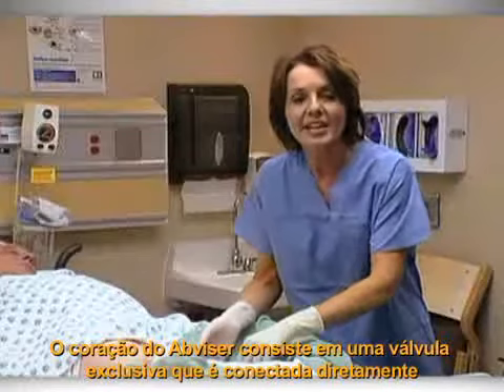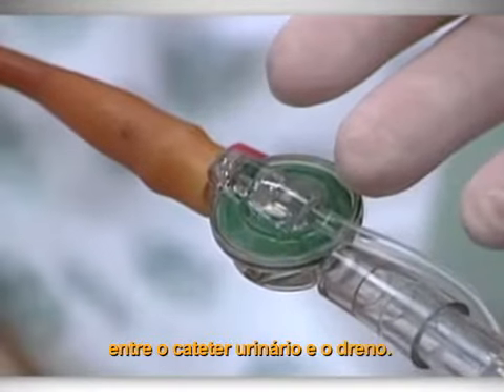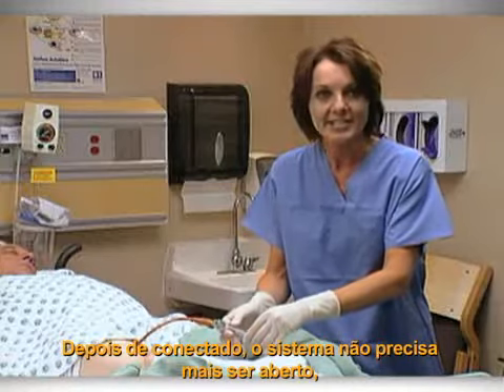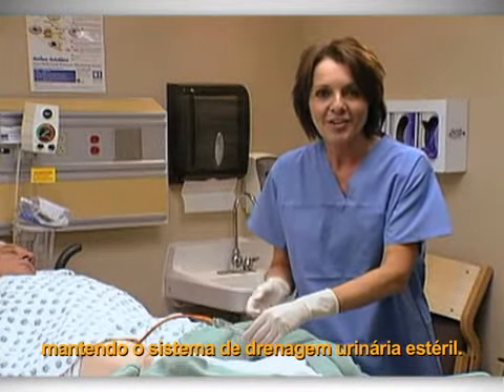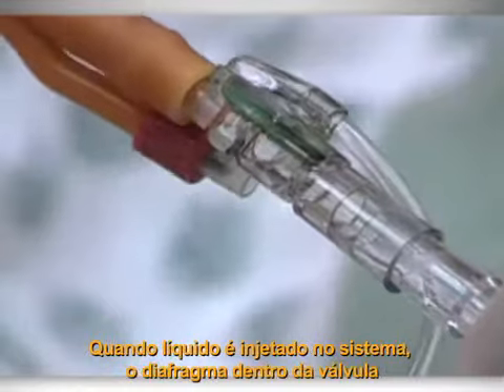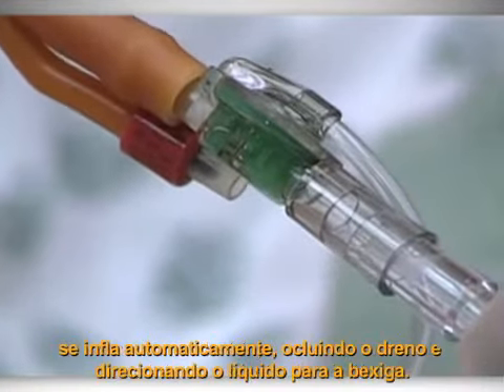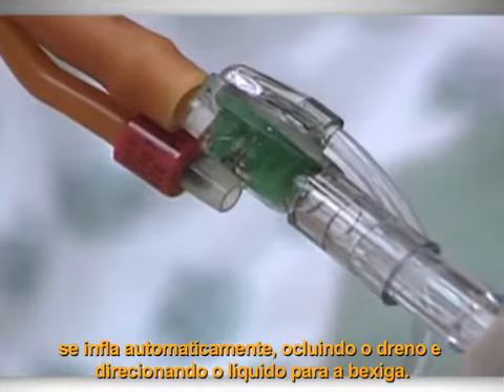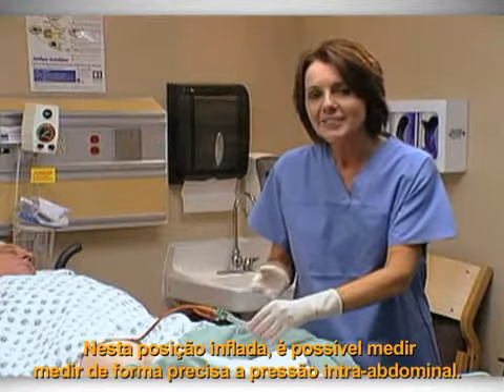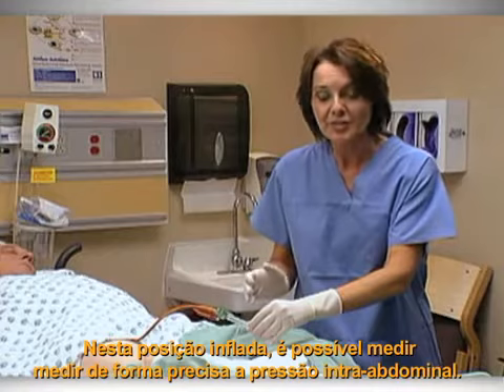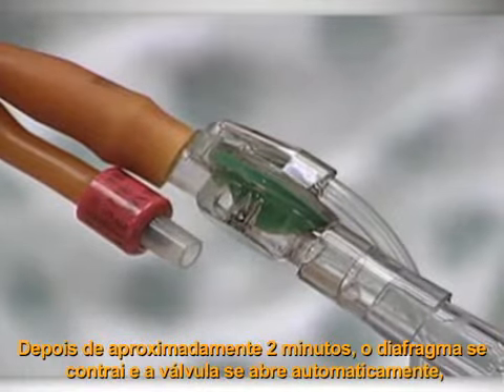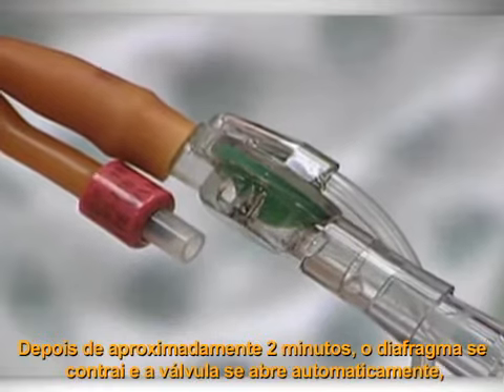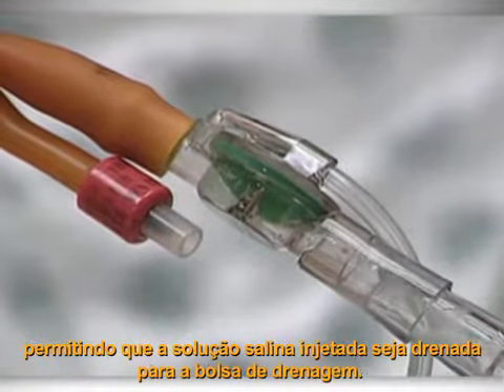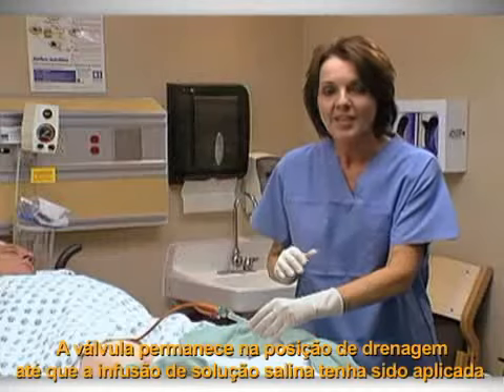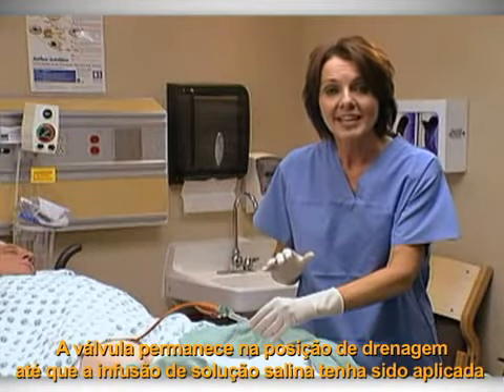The heart of the Abviser is a unique valve that connects directly between the urinary catheter and the drain tube. Once it is attached, the system never needs to be opened again, maintaining a sterile urinary drain system. When fluid is injected into the system, the diaphragm within the valve is automatically inflated, occluding the drain and directing fluid into the bladder. In this inflated position, you are able to accurately measure intra-abdominal pressure. After approximately 2 minutes, the diaphragm collapses and the valve automatically opens, allowing the injected saline to drain into the drain bag. The valve remains in this drain position until you infuse saline to obtain your next trending data point.